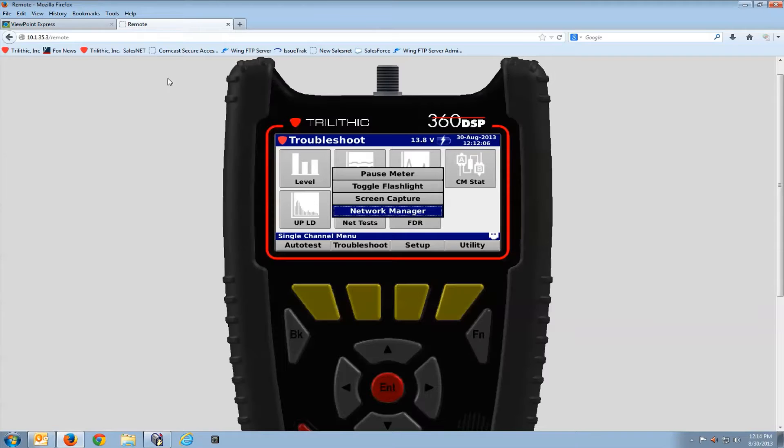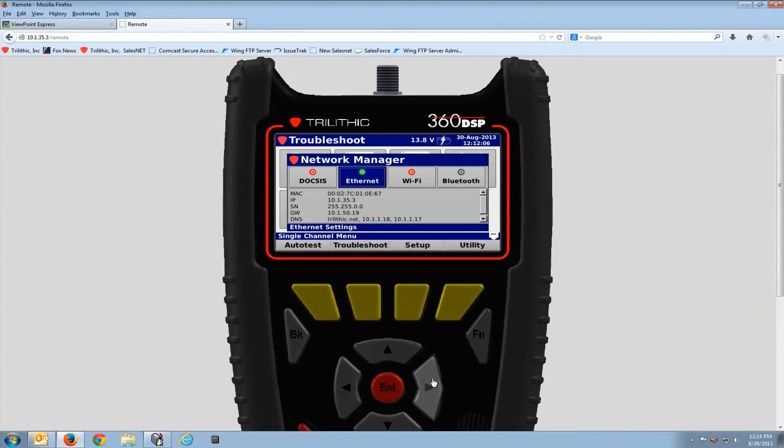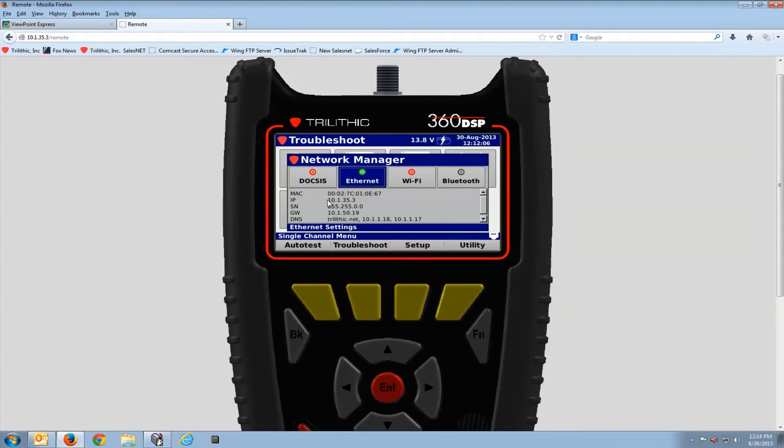The first thing I need to do is get my 360 online. In this case I'm connected via the RJ45 port or the Ethernet. You can connect your meter online through the cable modem, RJ45 port, or WiFi, as long as it's on the same network or accessible from your PC that the Viewpoint Express software is on. So in this case I can see my IP address is 10-1-35-3.